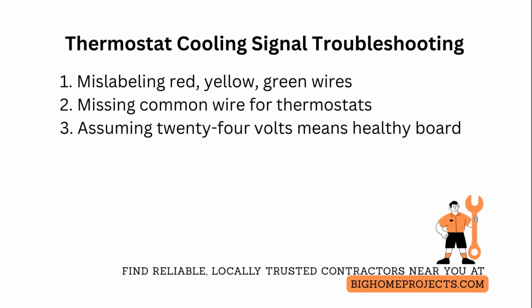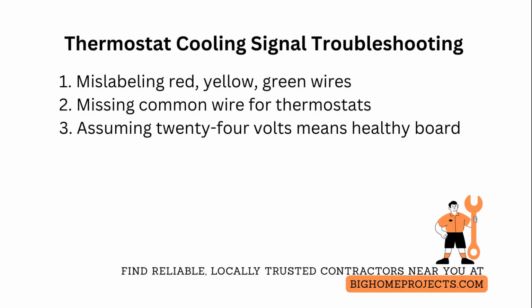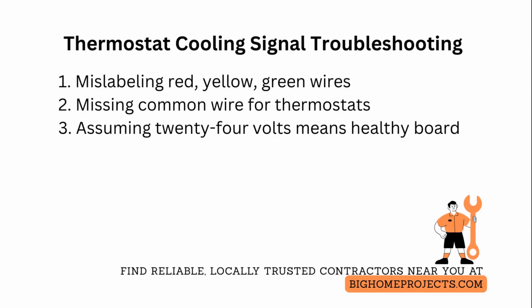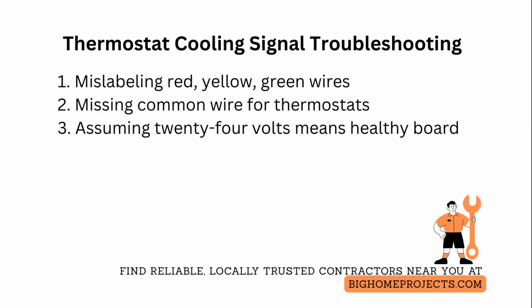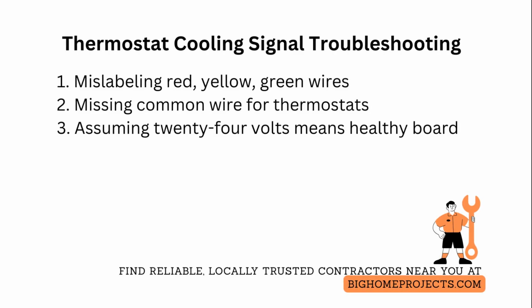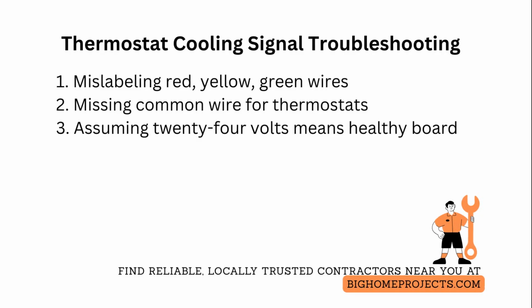A third typical problem is assuming 24 volt presence at the thermostat equals a healthy control board. Voltage can be present at red but lost at yellow or green due to broken traces or bad terminals. Trace voltage all the way to the control board. Inspect screw terminals for corrosion, and test relays and contactor coils directly.